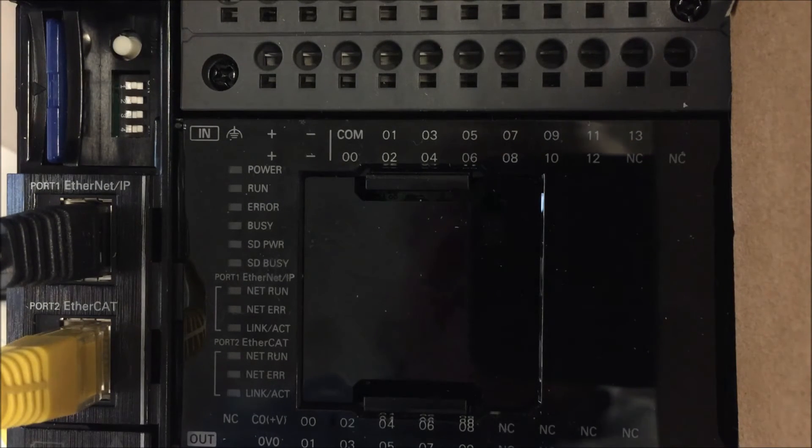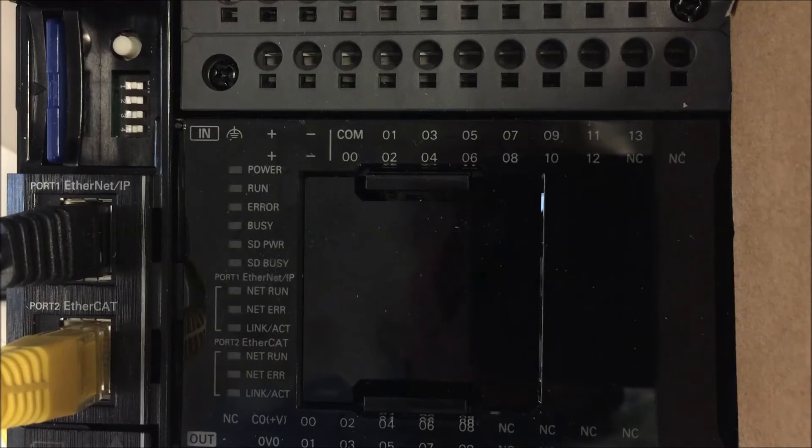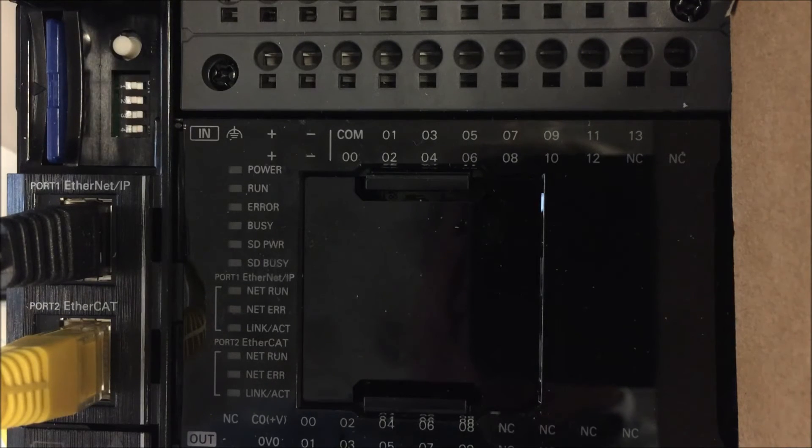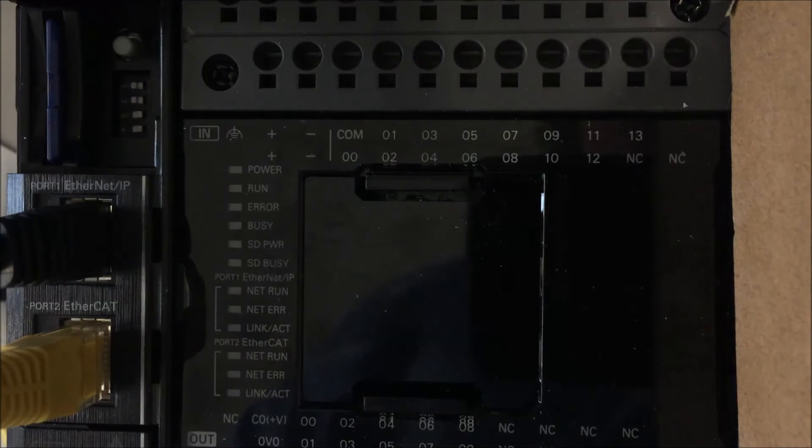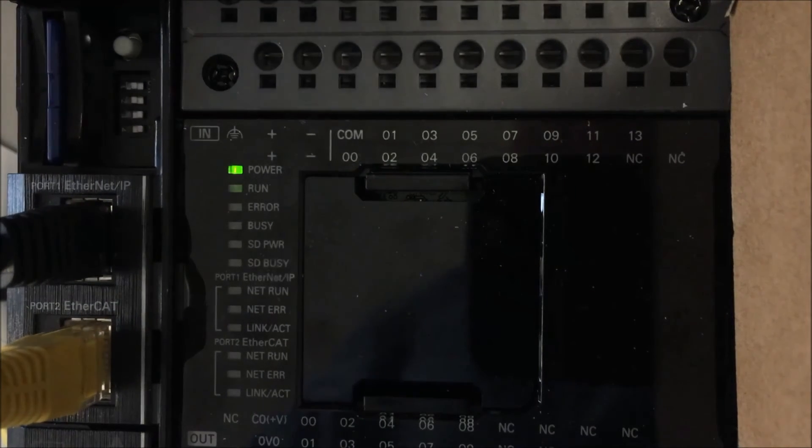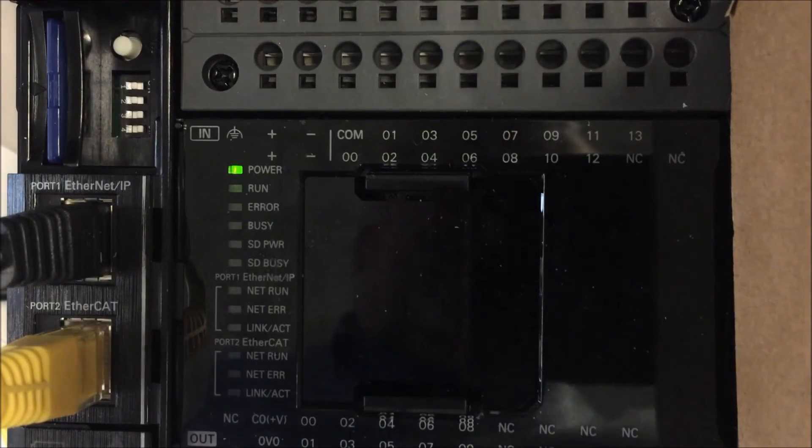I've turned off power to my PLC, inserted my SD memory card and set dip switches 3 and 4 on. Now I'll turn on power and it will go through the restoration process.